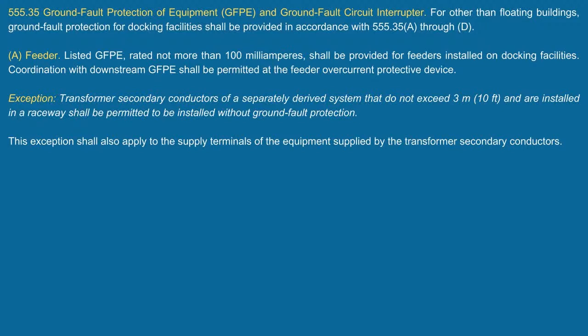Okay. GFCI everything. First, I wanna bring a point up here. He says at a point where it receives its supply is the outlet, and then he says at the receptacle, like if you were cord and plug connecting it. Well, first of all, a receptacle is a device. It's not an outlet. There's a reason that we have a definition for a receptacle outlet, which is the box, and then you have a definition for a receptacle. The outlet is the box, okay? And that's why these terms are going to matter when we're looking at this.